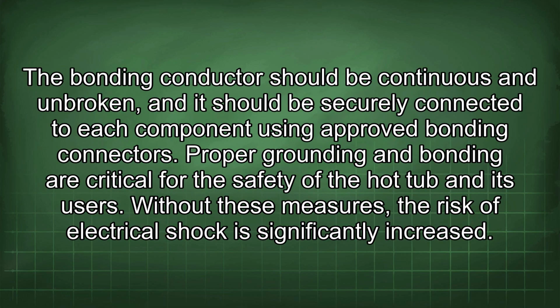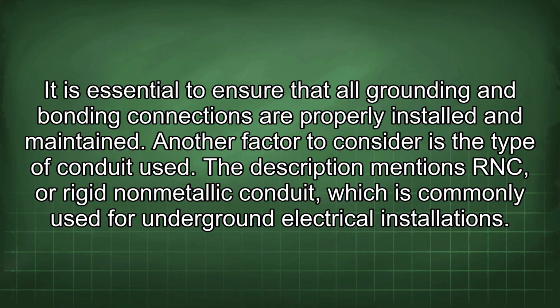The bonding conductor should be continuous and unbroken, and it should be securely connected to each component using approved bonding connectors. Proper grounding and bonding are critical for the safety of the hot tub and its users. Without these measures, the risk of electrical shock is significantly increased. It is essential to ensure that all grounding and bonding connections are properly installed and maintained.